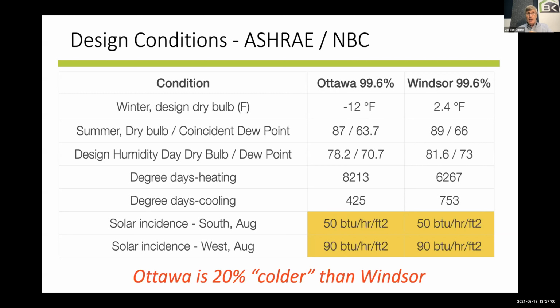That means any air coming from outside that hits a surface cooler than 71 degrees, 70.7, is actually going to condense. Look at the design humidity day in Windsor, that's 73, 74. Are there any surfaces in your houses that are cooler than, in this case, 71 or 74? And the answer is lots of surfaces. All my cold water pipes.